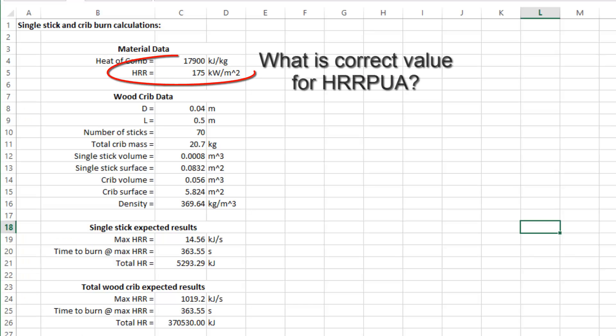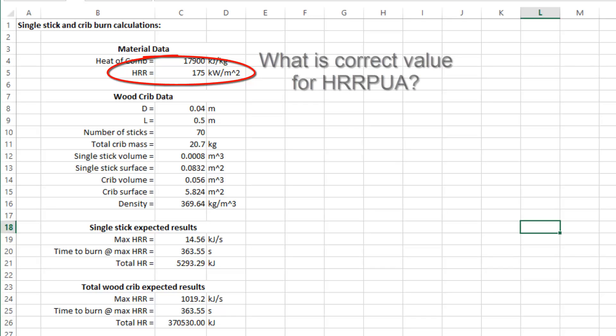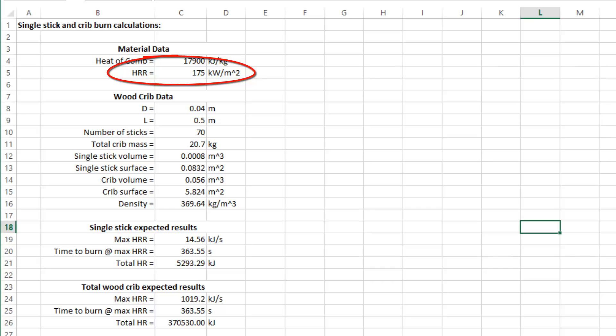The large uncertainty is how to define the heat release rate per unit area after ignition. For this first calculation, I assumed a value of 175 kilowatts per square meter based on peak heat release rate data in a paper by Michael Spearpoint. But, as could be expected and will be shown, use of peak release rate resulted in too high a heat release for the wood crib simulation.